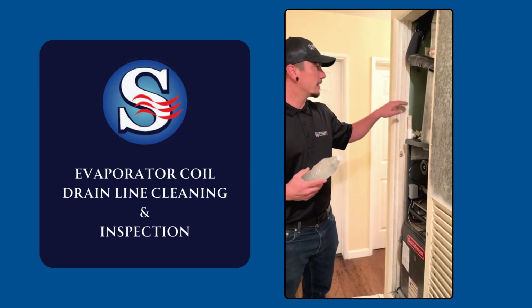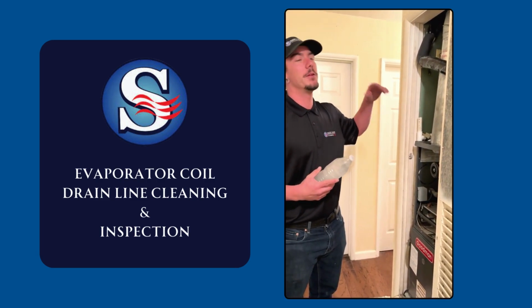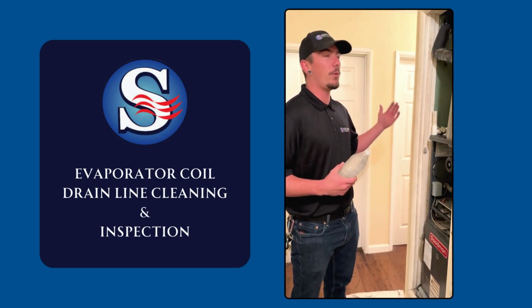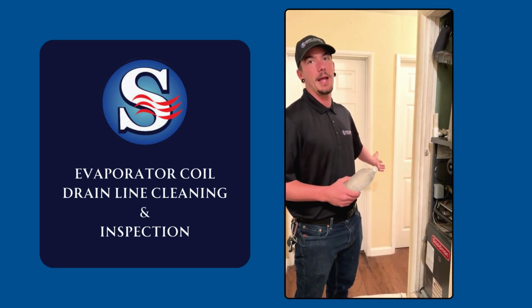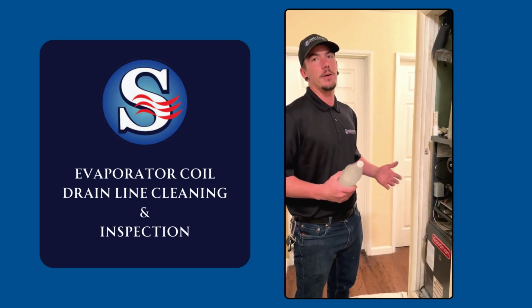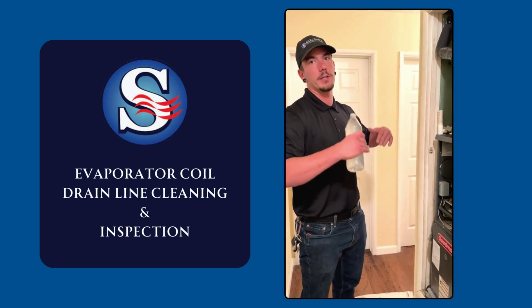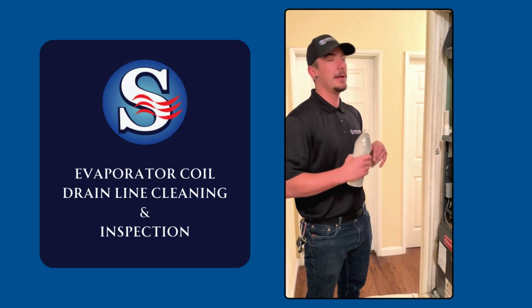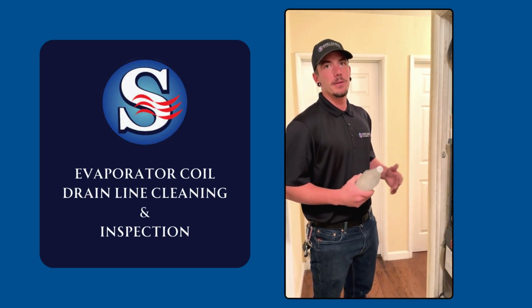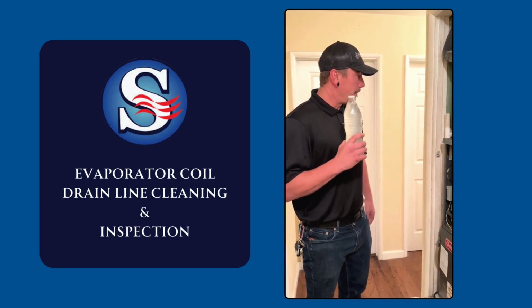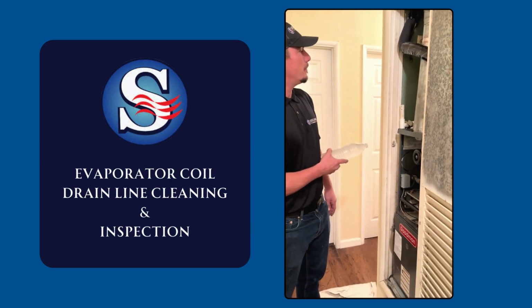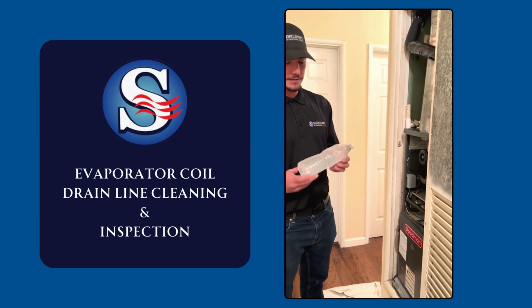It's also important to find the termination point of the drain line to make sure that the water you pour in is actually coming out. Some drain lines don't have proper fall, so the water will get trapped inside the pipe, causing severe buildup and blockage. This system, like I said, is on a pump, so I'm going to use this solution.